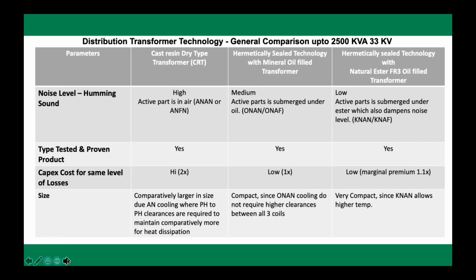The major issue nowadays started coming in Mumbai-like atmosphere, and that's the reason crowded cities like Mumbai have started moving away from dry type, and that's the latest trend you find with the Tata Power or Reliance. They started buying distribution transformers, copper wound distribution transformers with K class. Now, why I'm saying copper wound here is because these transformers can also be made with aluminum, but they become bulkier. Bulkier in the sense, not in the weight, but in the size. And Mumbai-like atmosphere doesn't have that type of space available for the distribution transformer installation.